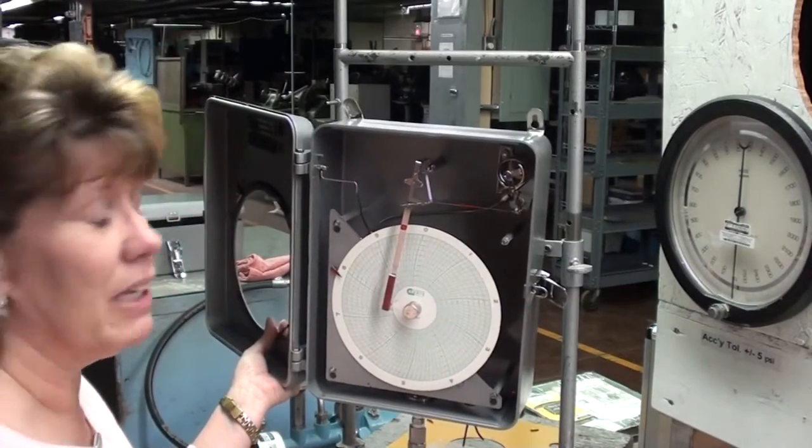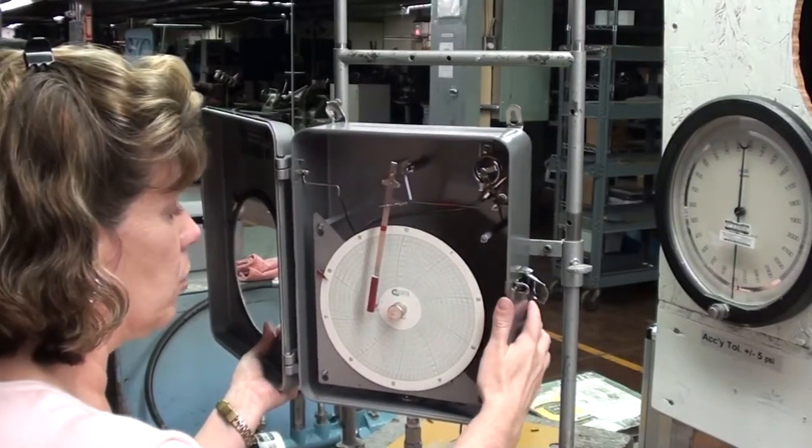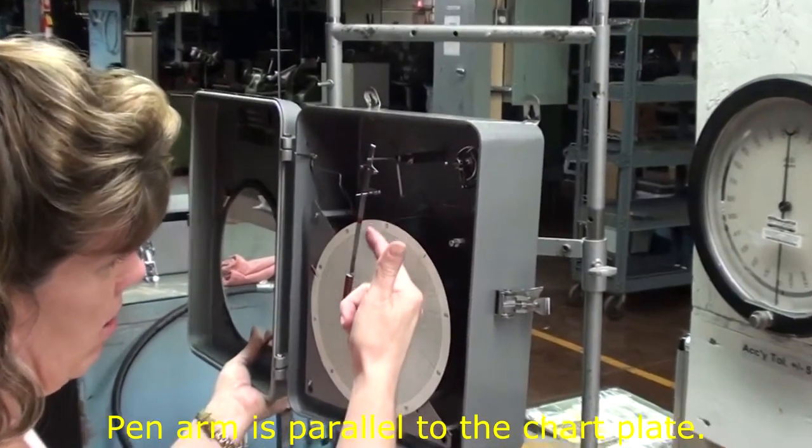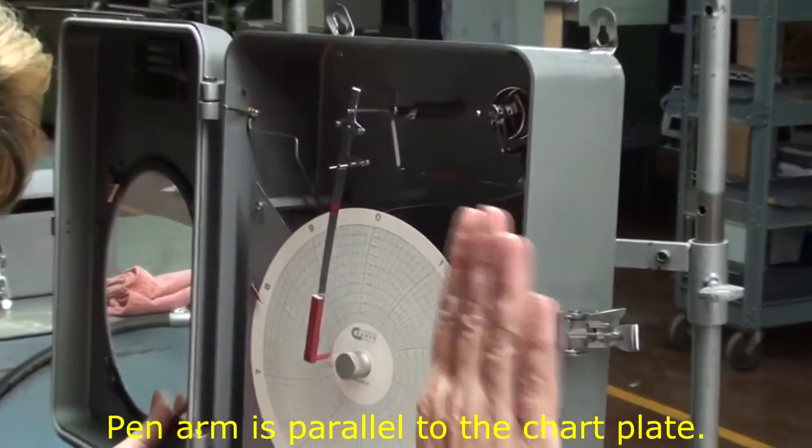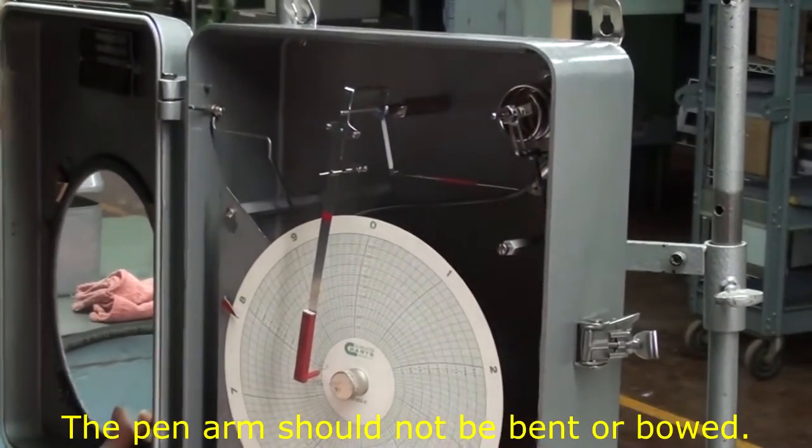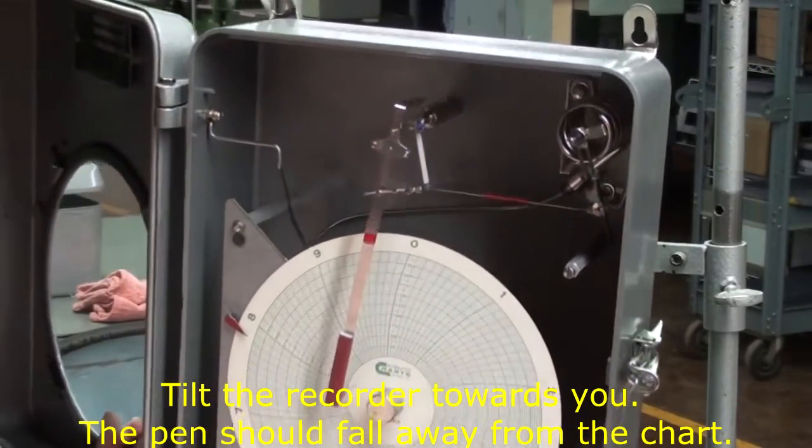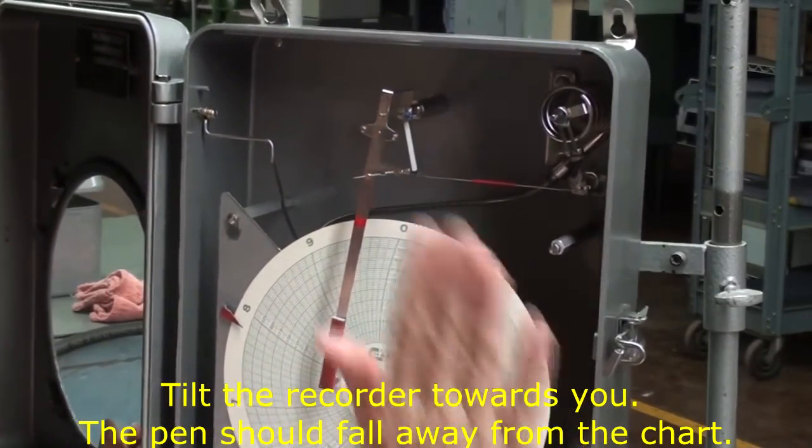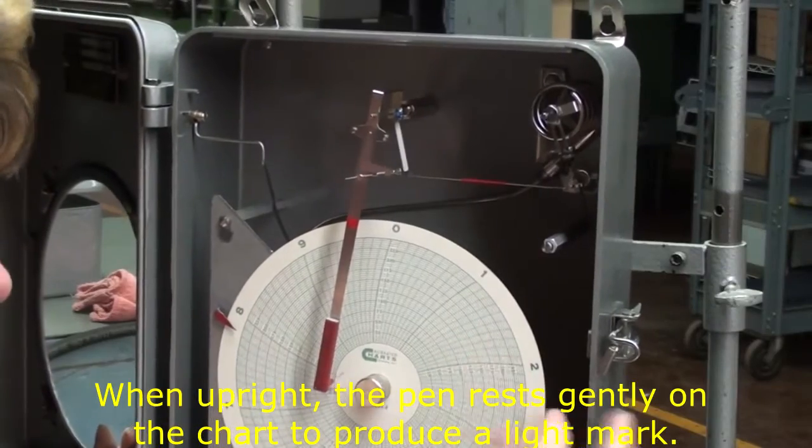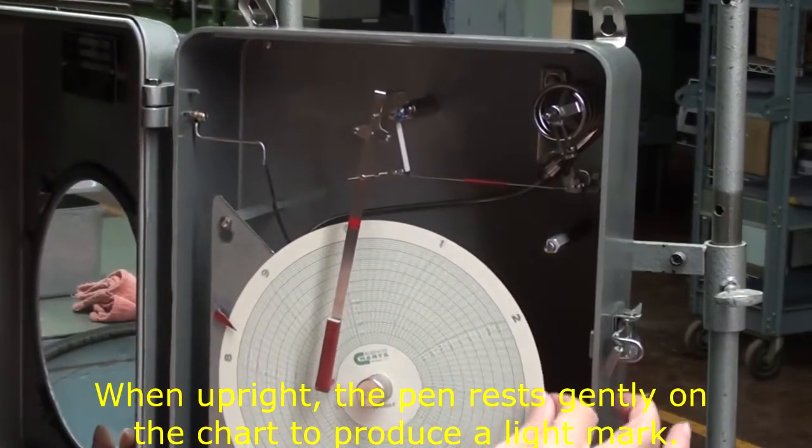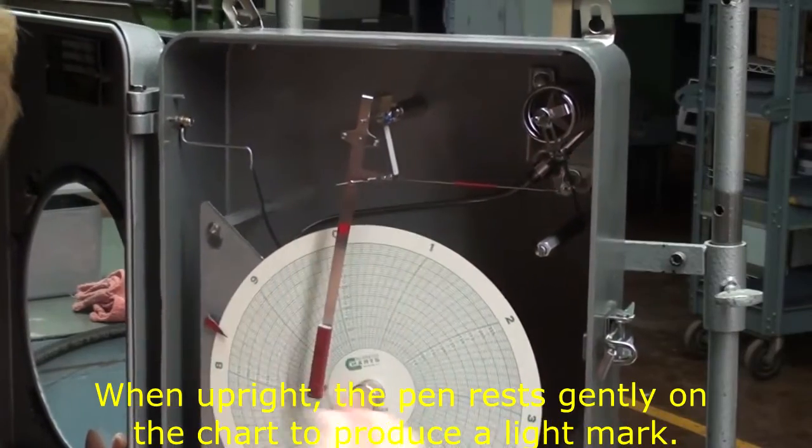Okay, we now have the pen tension correct. And if you will notice, the pen arm itself is parallel to the chart plate. We've not bowed it, put a hump in it or anything. And then if you tilt the recorder forward, the pen gently falls off the chart. But when you put the recorder back upright, the pen then sets back on the chart and marks. And you don't want a real heavy mark. You want a gentle, light mark.